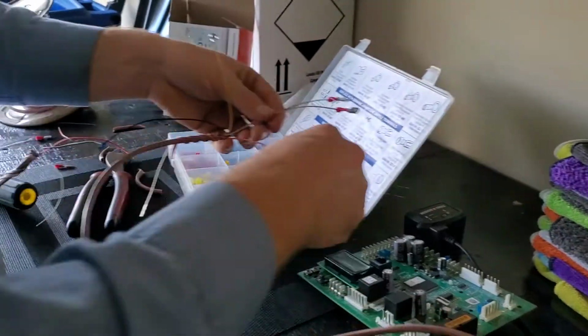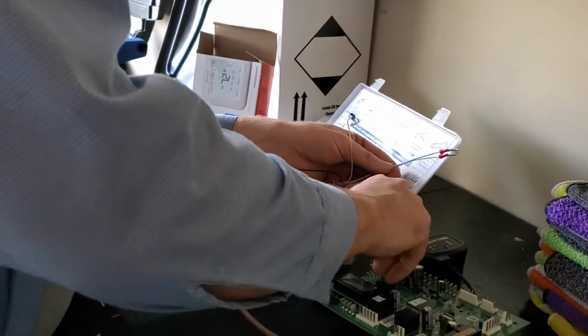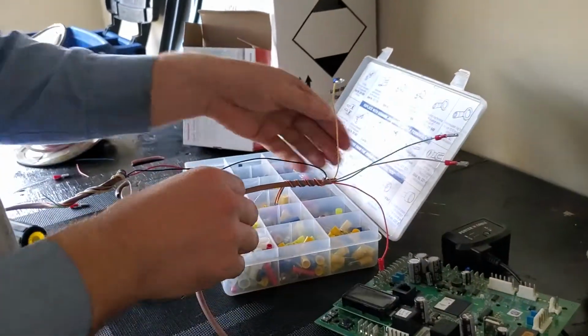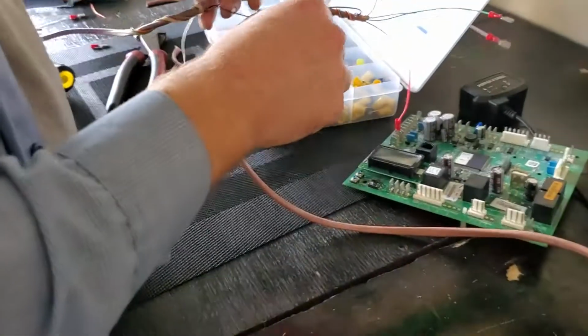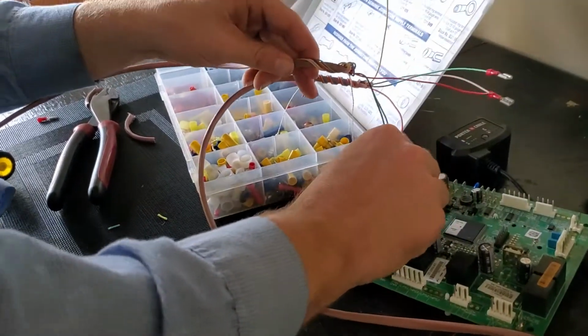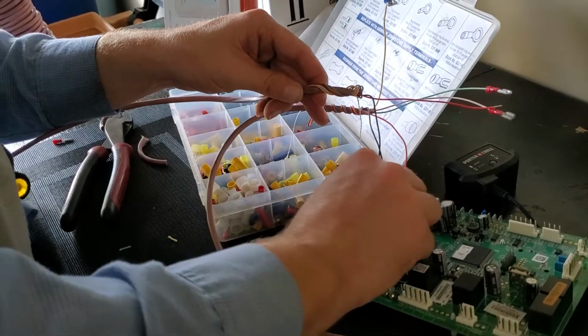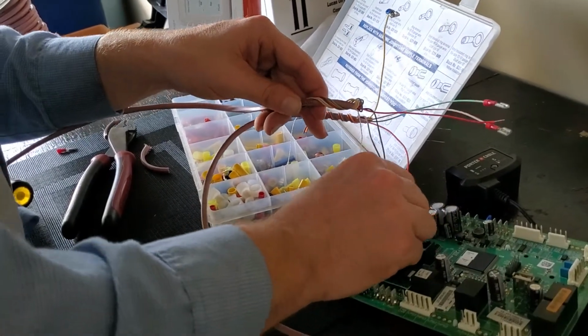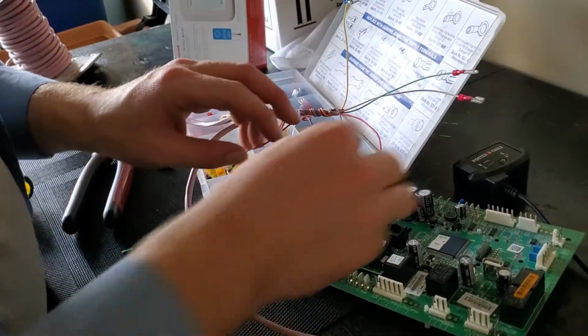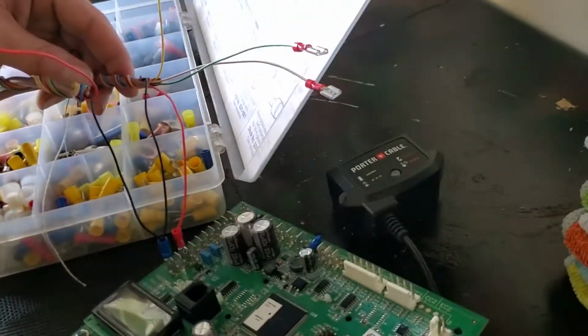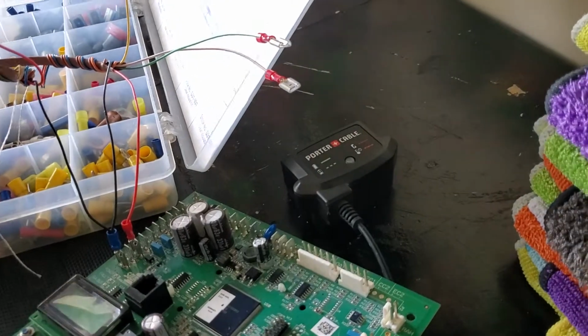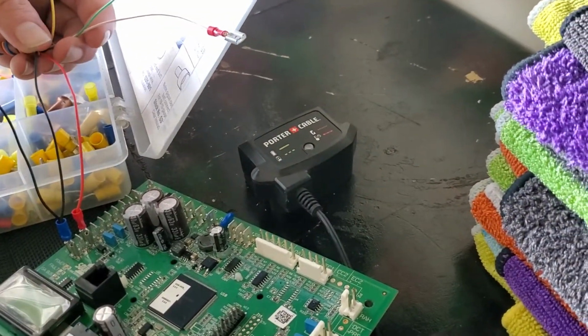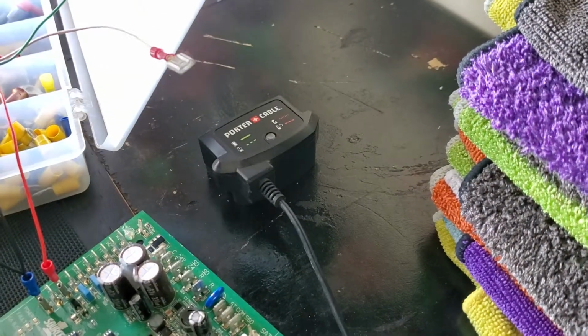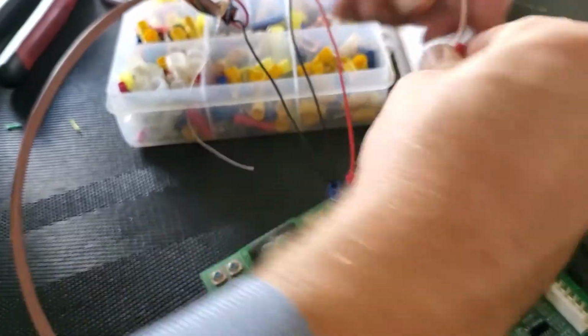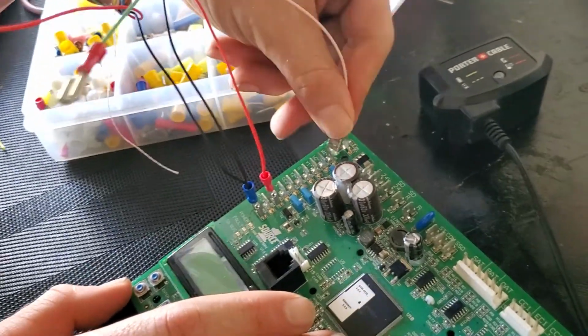So you've got your red and common. That's sending power to the thermostat, 24 volts. So if you just had these two wires hooked up, your thermostat would light up, but it wouldn't do anything - it doesn't have any... right. So if you just had those two hooked up, your thermostat would power up, but like I said it wouldn't do anything. Okay, and then you've got heating, W1 - how do you remember that heating is white? Is there any kind of...